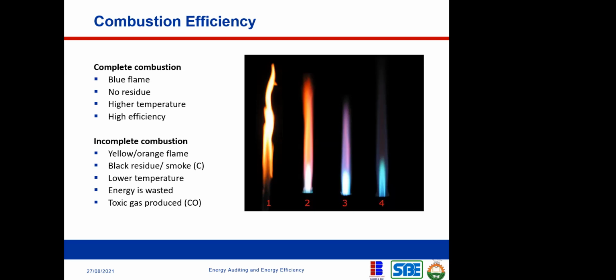Okay. Whereas number one, not all the fuel was burnt to release its energy content. So some of the fuel just came in and also left, so the energy content was not realized. That's what number one really means. And if you look at the description I have here, complete combustion, you have the blue flame, which is number four. You have no residue, so the fuel is completely burnt. You have a higher temperature because the fuel releases all of its energy. Then it has a high efficiency, right?